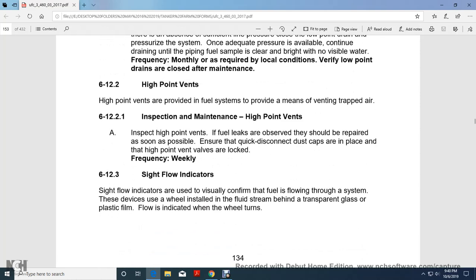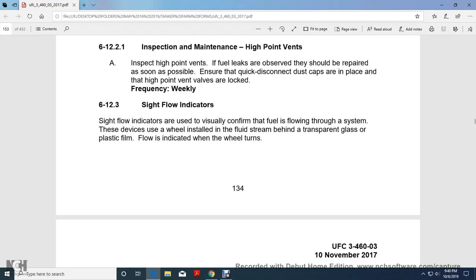6.12.2 High point vents. High point vents provide the fuel system a means to vent trapped air. Inspection maintenance: fuel leaks observed at high point vents should be repaired as soon as possible. Ensure the quick disconnect dust caps are in place and the high point vent valves are locked, weekly.